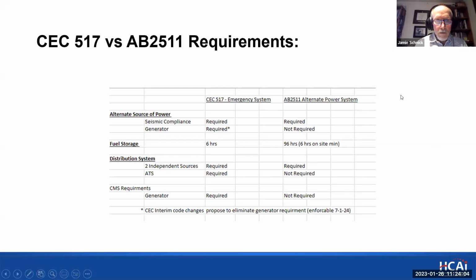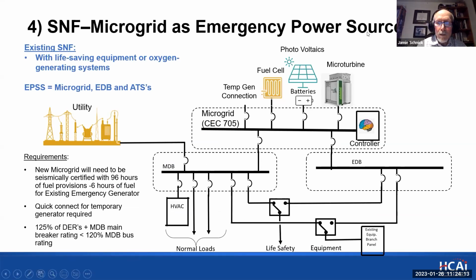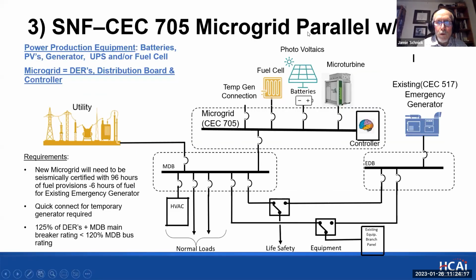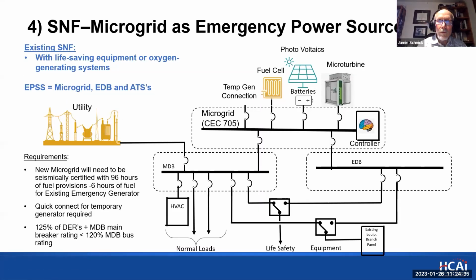The reason I point this out, and once I show the next diagram, I'm going to ask Walt to jump in and talk about the current condition of codes and the evolution of codes as we see it, is that the solution we saw previously in number 3, which is completely independent and not part of the emergency system, still has the requirement of the emergency system to have special seismic certification. And so eventually we think, as a future option, that this solution could transition to also provide emergency power, which would allow the generators to not be required. In this case, all the requirements of 517 would be met. The sources are seismically certified, the fuel is over 6 hours, which is the only requirement for emergency power, and the system is completely independent.